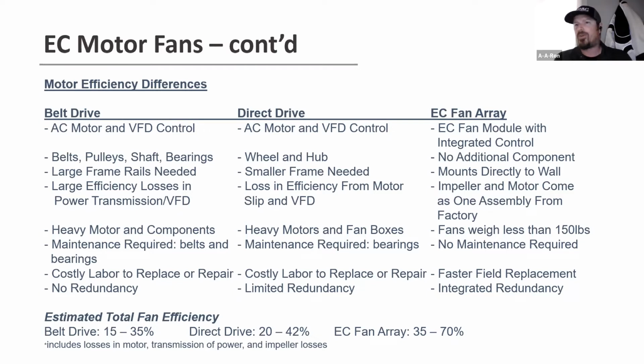So you don't really find that with a belt drive system, or even with something like a Nortec system where they're using 3 or 4 cubes. You're really dividing that load into threes or quarters. Total fan efficiency can get anywhere from 35 to 70% total fan efficiency, which is twice as high as you would probably get on most other options.